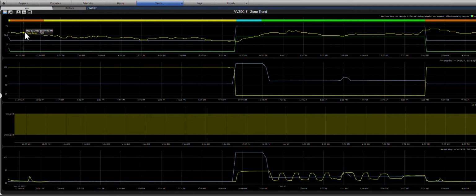All right, so we were in the orange. This is spanning left to right about a 24-hour window for the zone. We can see we were 73 yesterday. We were cooling down. Here was the optimum, cooling. It was 71 or below. We wanted to be between 68 and 71 here. We were yellow till we started to creep down, and finally we got to the area where we could start to turn green. This should have reflected it. I have a feeling this is probably a delay or a hysteresis, a kind of dead band, to make sure we were in it before it actually turned green.